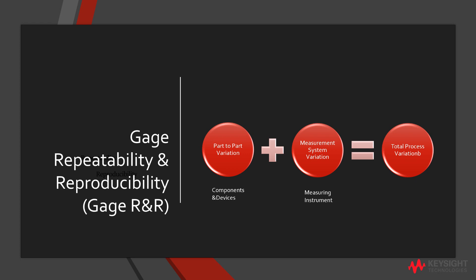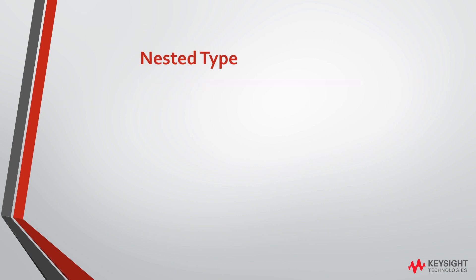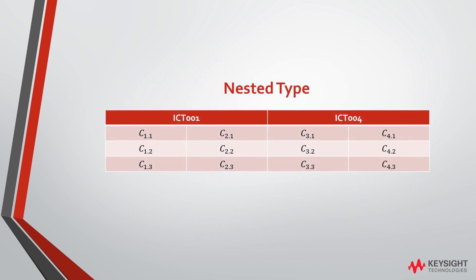One is the nested method and the other is the crossed method. The nested method is applied if successive testing of a part alters or damages the value of the part. With measurement from ICT001, Component 1 has been tested three times to check if the variability of Component 1 is acceptable, which is repeatability.